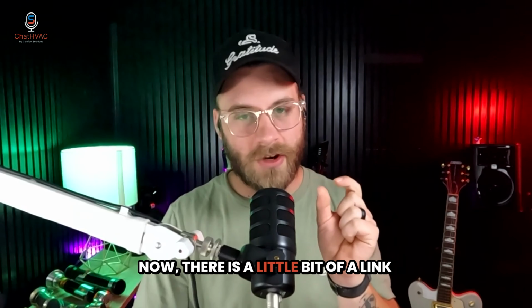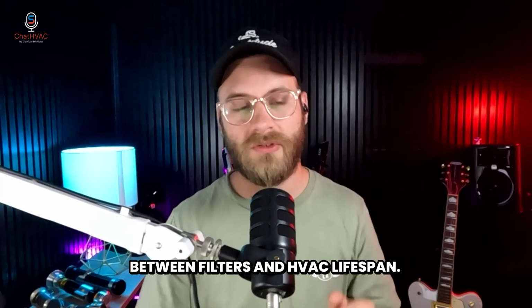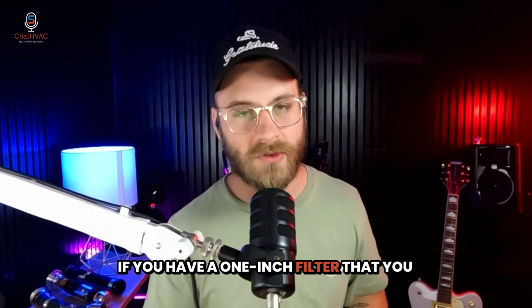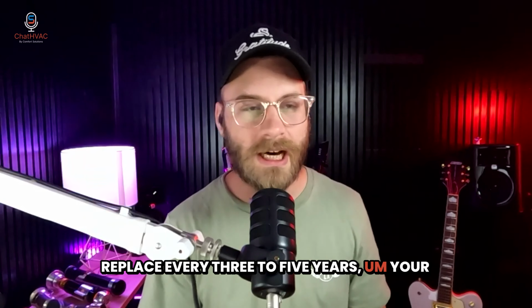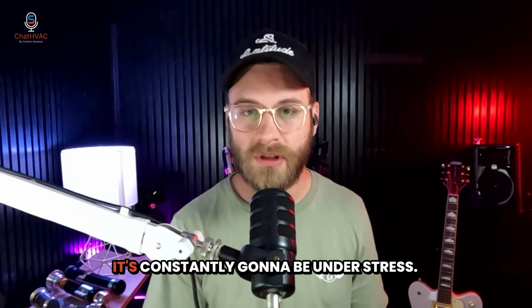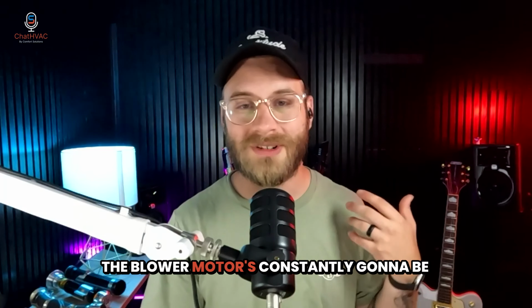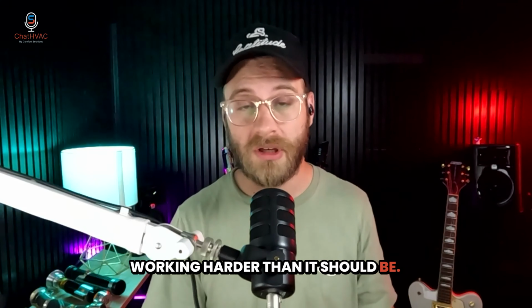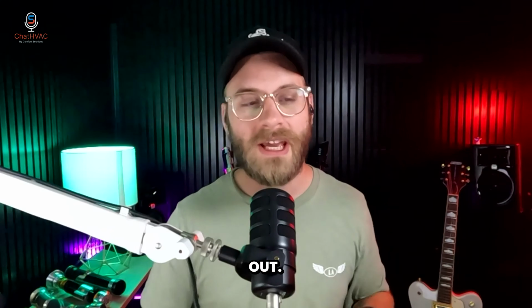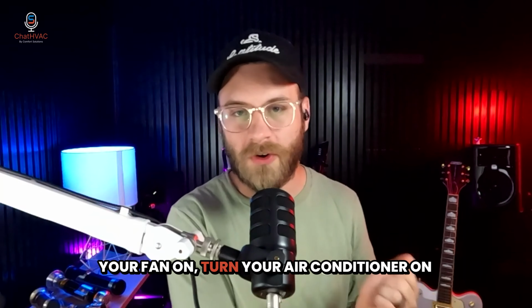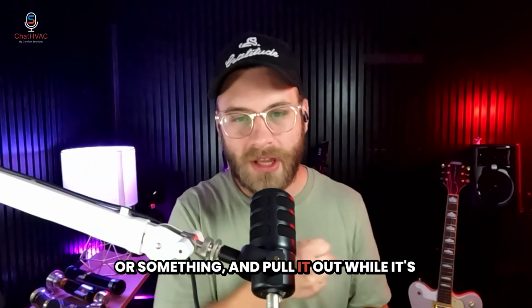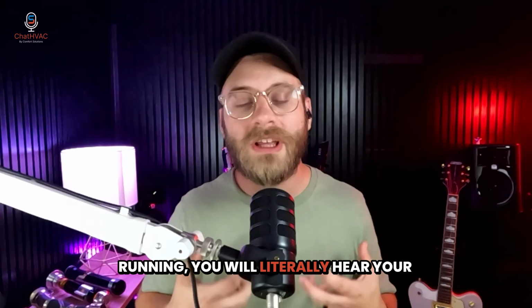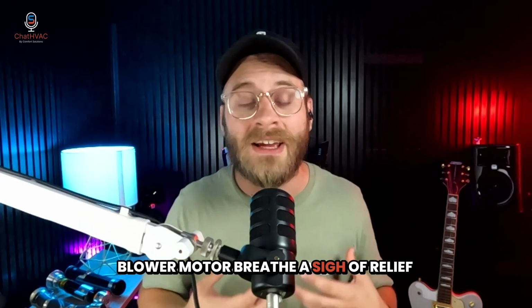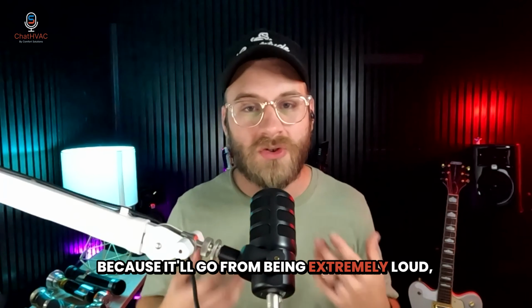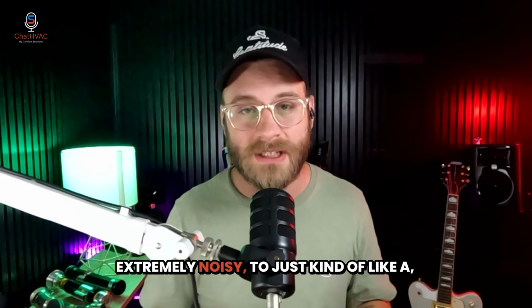Now, there is a little bit of a link between filters and HVAC lifespan. If you have a 1-inch filter that you replace every 3 to 5 years, your system's probably going to struggle. It's constantly going to be under stress. The blower motor's constantly going to be working harder than it should be. When you finally pull that dirty filter out, if you ever have a plugged filter, turn your fan on, turn your air conditioner on or something, and pull it out while it's running, you will literally hear your blower motor breathe a sigh of relief because it'll go from being extremely loud, extremely noisy to just kind of like, oh, thanks for that.